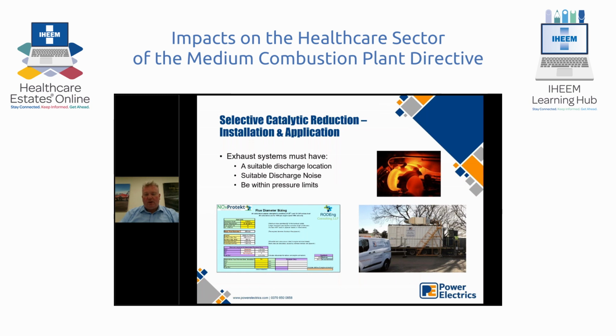There's a couple of case studies in a minute which will show you how they look on larger generators. You can put them however you want, but particularly in a plant room, if there's not a lot of room above the generators, it can be quite difficult to fit the SCR systems in. This is where experience comes in, so as not to reduce the integrity of the existing system and to maintain it.